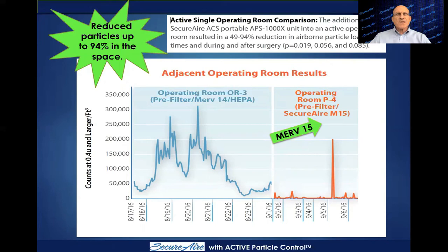And in side-by-side comparisons over a week's period of time, we reduced the number of particles in the air by 94% compared to conventional operating room technology, 18 air changes an hour and a MERV 14 filtration device. Incredible performance, apples to apples comparison, validated, published. This is fact.